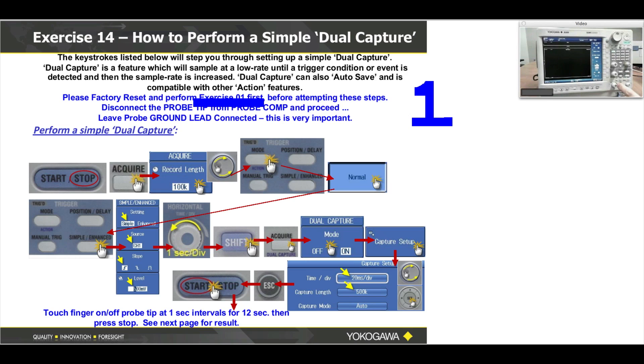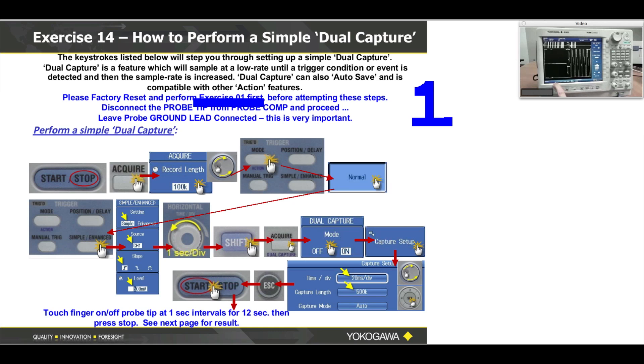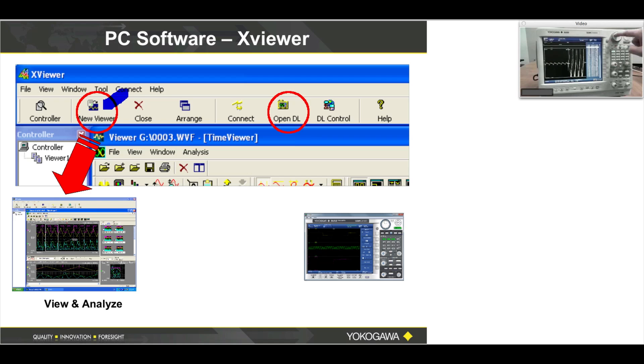There's nothing on my probe, no noise — but now when I expose the probe tip and touch it, I create a capture. I'm going to hit it about six times. Make sure you're getting the same reaction on your instrument. At my fingertip here I have an acquisition count — I have 57 events. Everyone press stop. Soft menu button number four says list — press list. However many events you've got, I've got 87, so it's a total of 88 events, zero through 87.